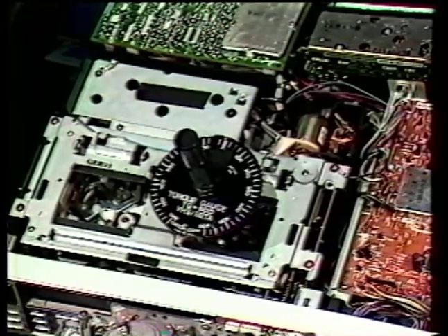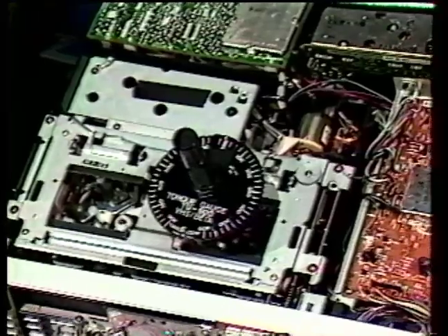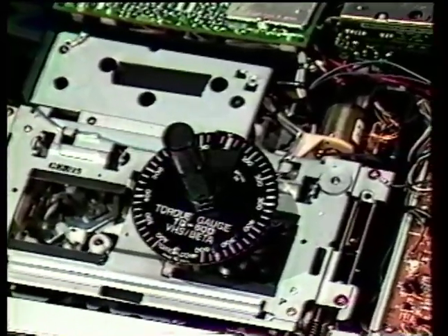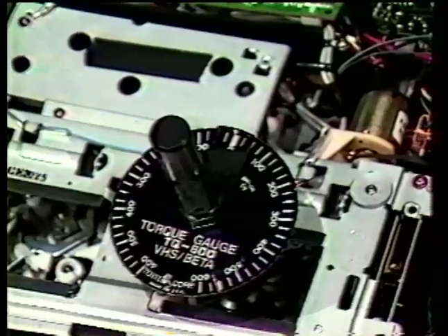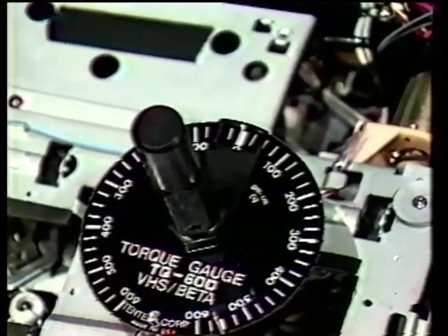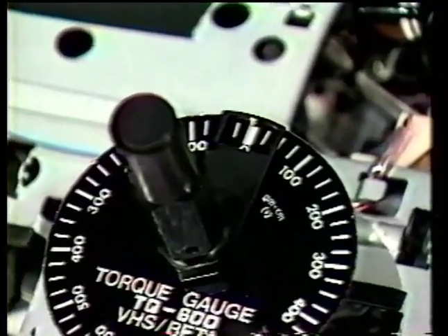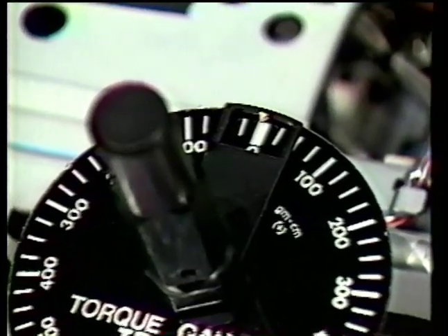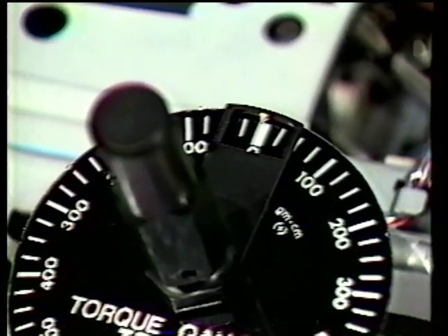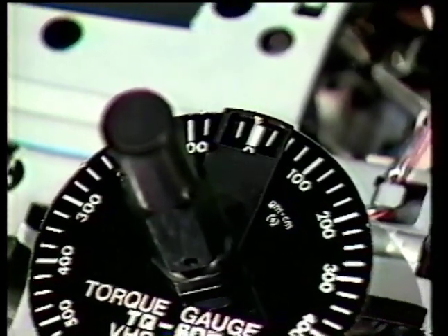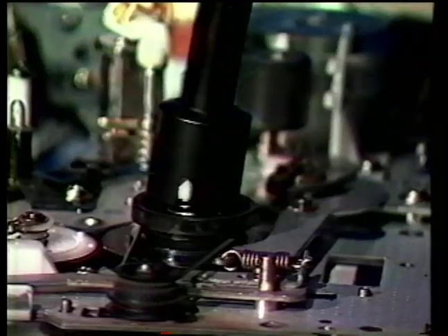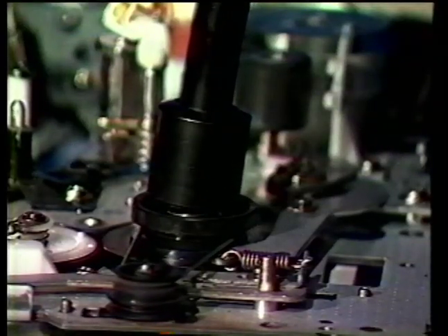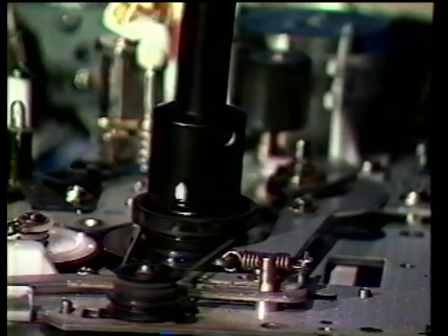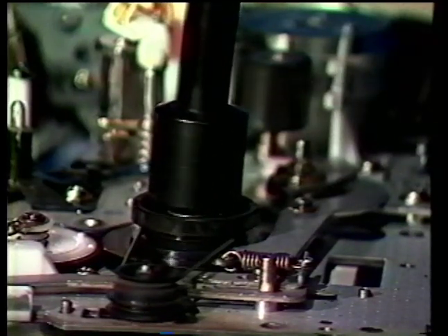Some of the advantages of the TQ600 are, first, it's got a larger, easy-to-read dial. The gauge is extremely rugged since it's based on a torsion bar design, which takes a lot of normal abuse. It has a long snout, allowing the gauge to be inserted right through the sheet metal in most of the newer front-loading VCRs. It also has an integral adapter made from aircraft-quality aluminum, which takes, again, a lot of abuse, so that there's nothing to buy as far as extra adapters.